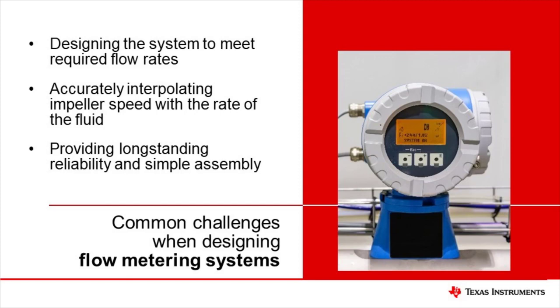Lastly, the long-term reliability of the magnetic flow meter stems from the contactless method of measuring fluid flow. The magnetic implementation has a longer device lifetime when compared to flow meters that operate on reed switches, which are susceptible to vibrations and have limited life due to the mechanical nature of the switches. Unlike the switches, magnetic sensors are not susceptible to breakage during installation and enable designers to create more compact designs.